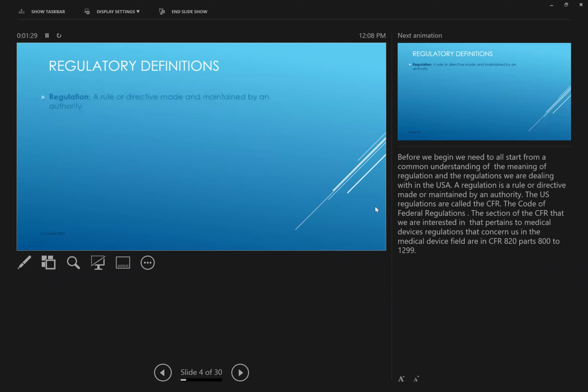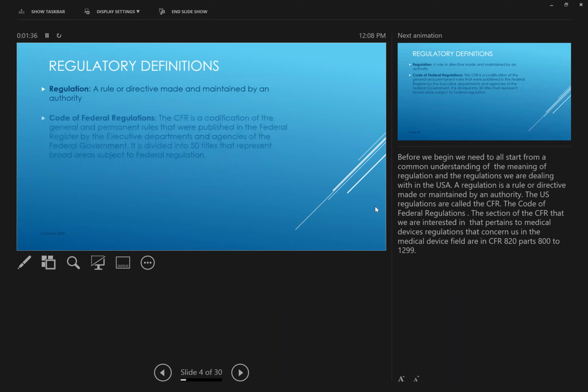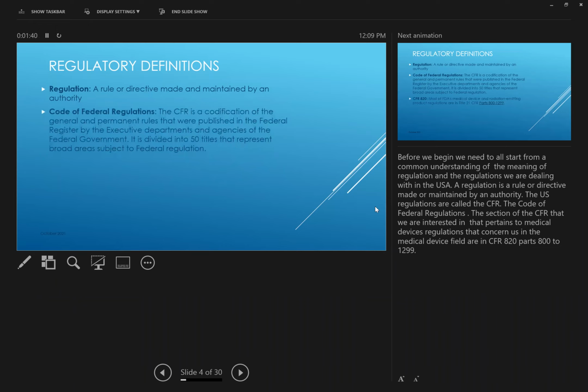I'll clarify what a regulation is: it's a rule or directive made and maintained by an authority. What applies to us is the Code of Federal Regulations. Again, you see the term CFR. The CFR is a codification of the general and permanent rules published in the Federal Register by the executive departments and agencies of the federal government. It is divided into 50 titles that represent broad areas subject to federal regulation. What we're concerned with is 21 CFR 820, which is applicable to medical devices and things similar to medical devices. So when we say CFR 820, we're talking about the regulations that, in regulatory, we have to be concerned with and meet the requirements of.